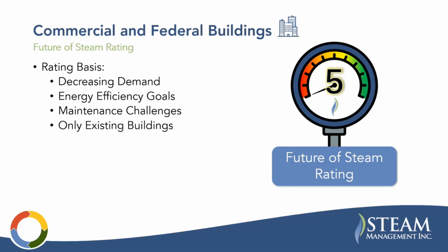So there is decreasing demand. Modern buildings favor hydronic or electric heating over steam. Energy efficiency goals of buildings. So the trend for high efficiency buildings is to move away from steam. Although it is possible for steam to achieve very high efficiencies, that's not the optics. Right now, everybody's kind of moving towards hydronic or heat pumps. And also high energy efficiency ratings such as LEED ratings. It kind of enhances the perception of the building and actually leads to increased revenue. So there's a lot of motivation to have efficient buildings. And so that's kind of leading to the decline of steam.